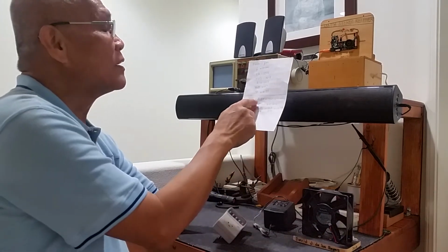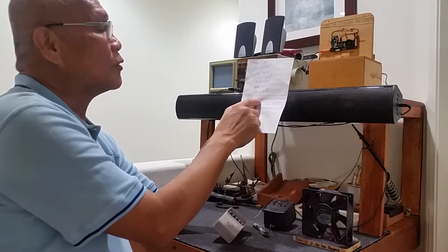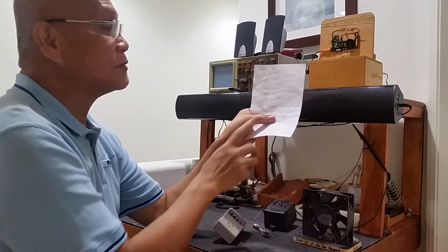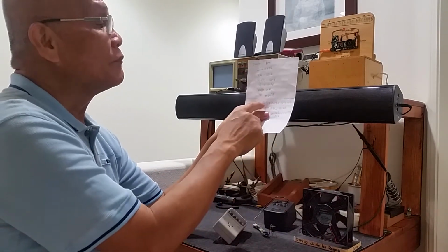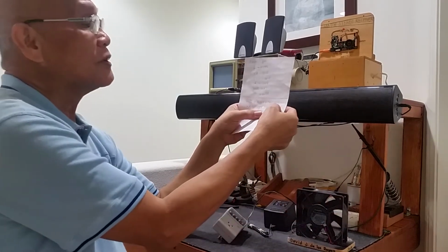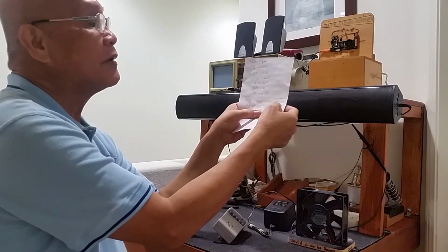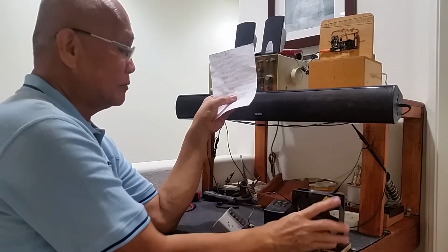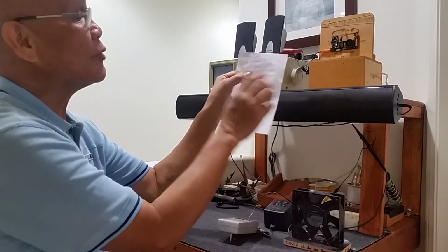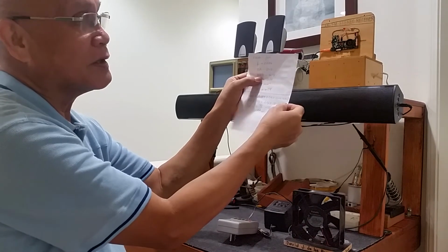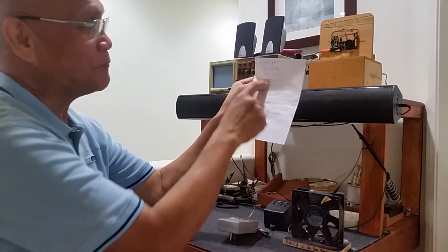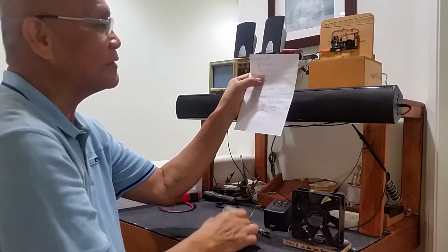Watts is the value of the volt ampere times the power factor. 15.4 times 0.79 for this load comes out to 12.12. When we plug in this load, what comes out is 12.3. So mathematically, as an engineer, I could verify if the reading is correct or not.